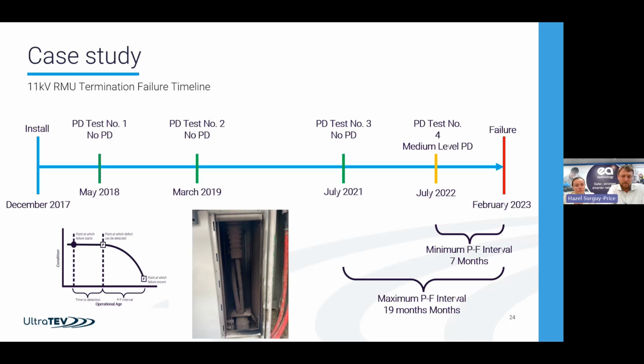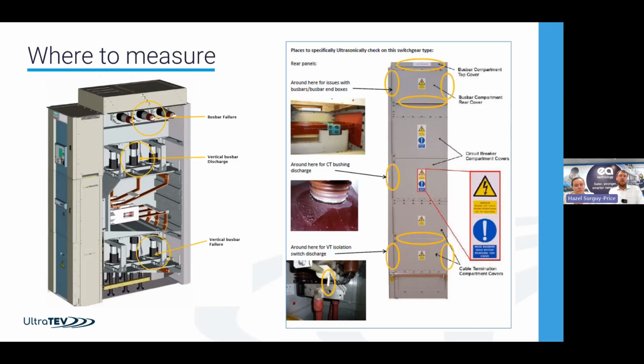So that's how often. The next key bit is where. Every switchgear has a generic approach, like we saw previously, where the moving parts are a higher risk. But there's also a history to this gear. There are thousands of units of most of this design across the network, and you aren't the first person to have operated or maintained that type of gear. So we need to lean on that knowledge bank.